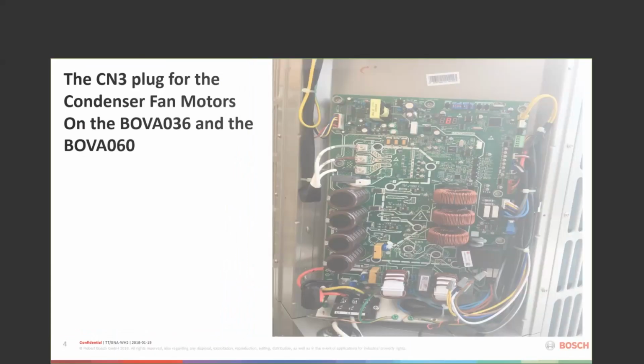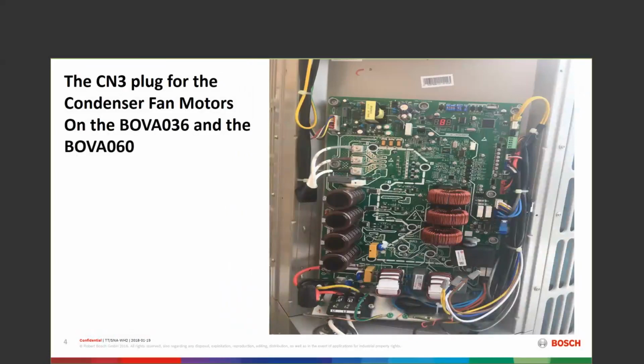Side of my board is the CN3 plug. That plug goes up to the, and is basically the Molex plug for the 10-speed condenser fan motor. Now, the 10-speed condenser fan motor is on the 3-ton and the 5-ton. So the 3-ton 1.0 was a 2-speed PSC motor. The condenser fan motor on the 1.0 5-ton was an 8-speed, but today on the 2.0 units, they are both 10-speed condenser fan motors.